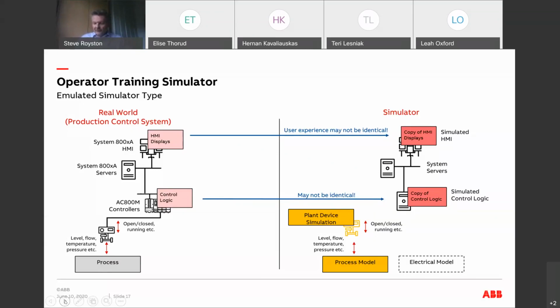Keeping them in synchronization is quite often a difficult task, because on the left-hand side, when you're commissioning the system and making the most changes to the real production system, you're also training your operators on the simulator to be ready for when the plant is available. So right when you're making the most changes in the real world, you want to reflect those changes across to the simulator world. That's quite difficult with an emulated system, because you're using different coding mechanisms, and making changes can take time.